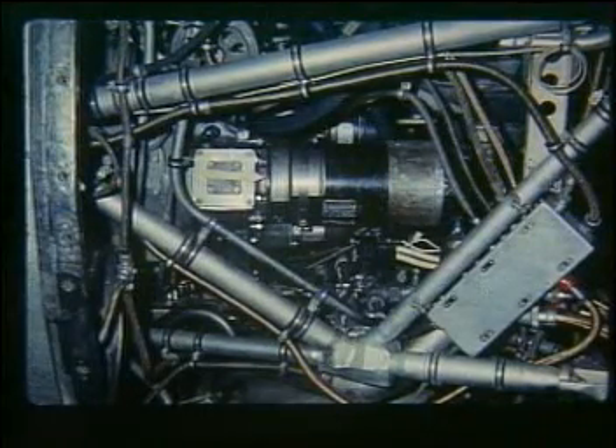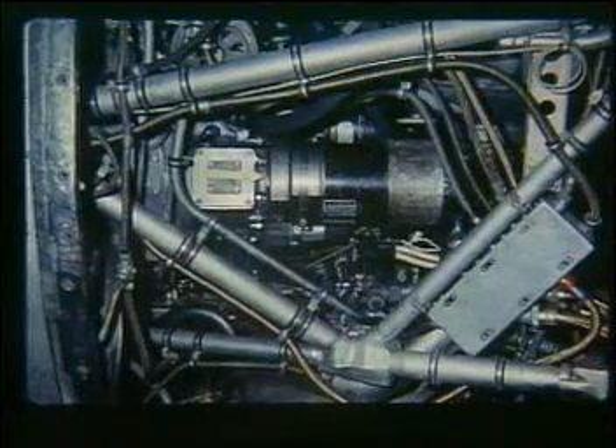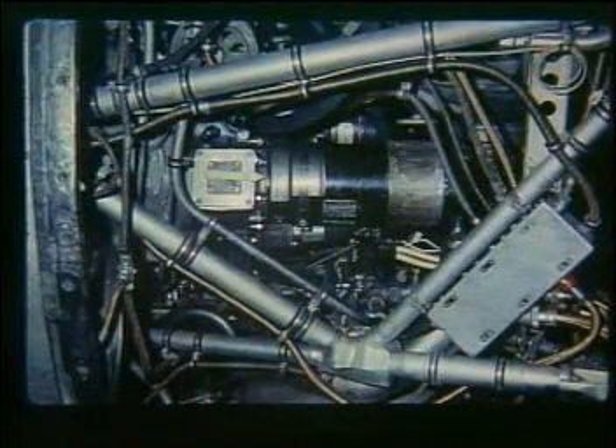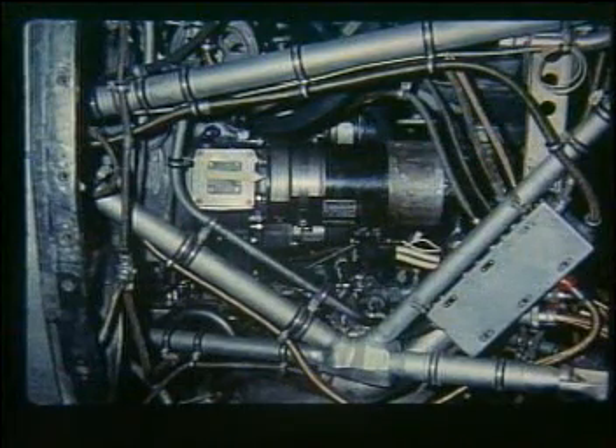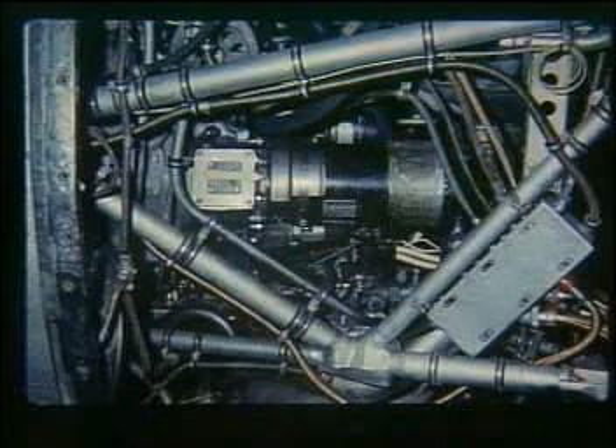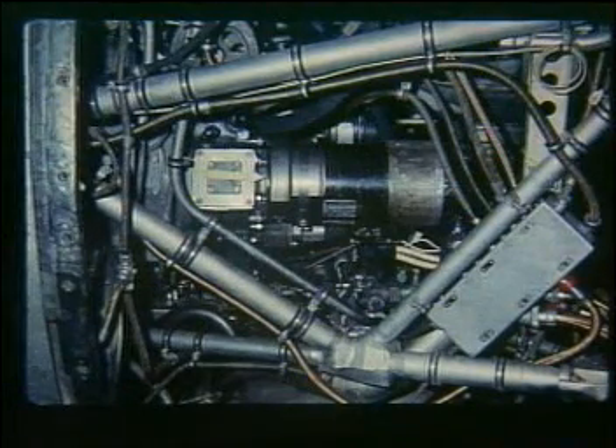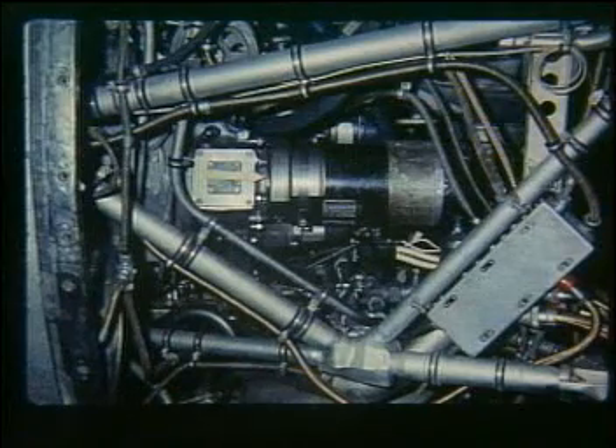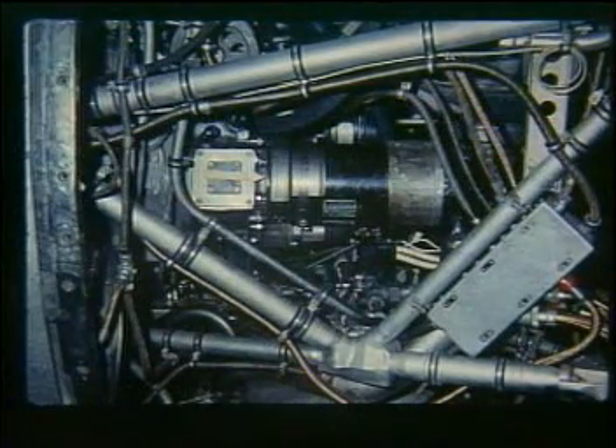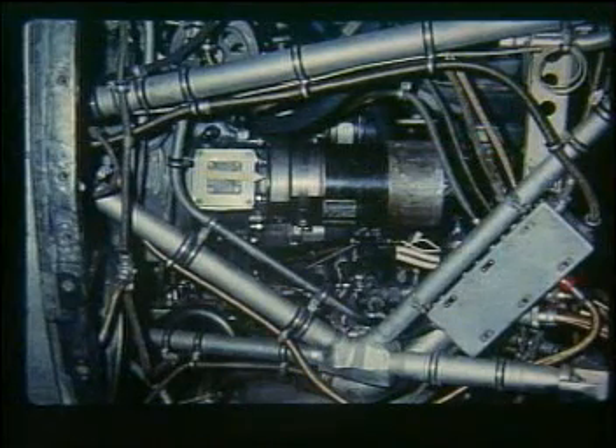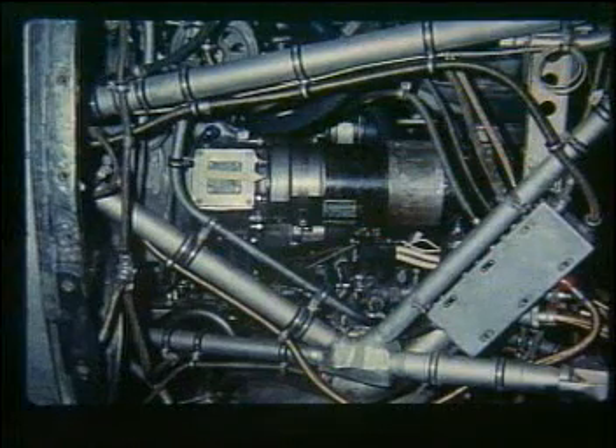Primary power is provided by a 28-volt DC generator rated at 300 amps. The generator may be operated at up to 450 amps for short periods of time if necessary. The output of the generator is to the master bus. The field of the generator is connected to the generator control panel in the voltage regulator compartment to provide a means of voltage regulation and control of the generator output.